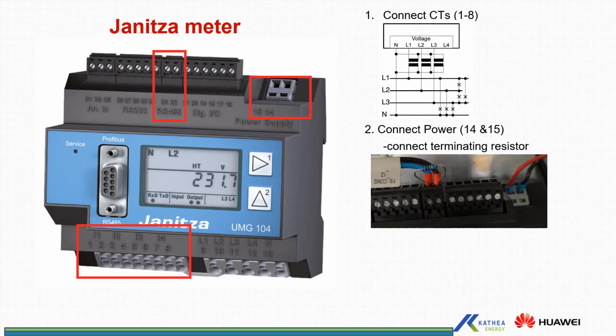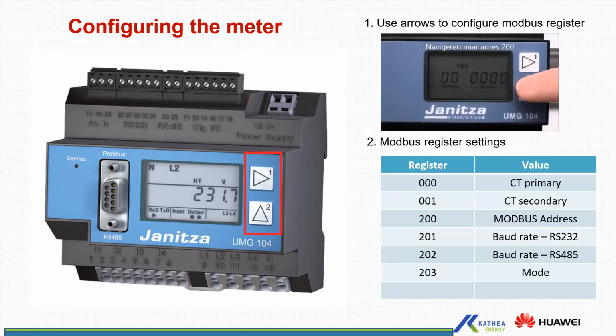The power meter, you need to supply with a 220 volts live neutral power supply, which is points 15 and 14 on the diagram for a 104. And then there is an RS485 port, which would be labeled A and B, which is 22 and 23. That's where you wire your comms cable that you would take to your logger or to your master inverter. For an Acrel, your master inverter has to be a 100 KTL inverter. Between the A and the B, you need to install a 120 ohm resistor supplied with the meter as an end of line termination.